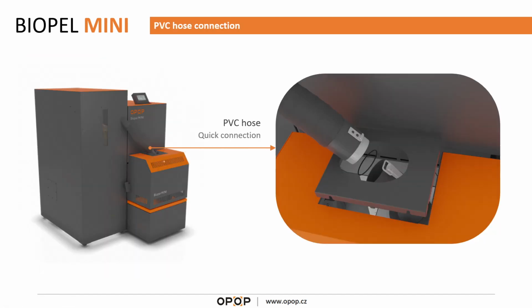Okay, like this. More about the installation on the 3D model of the boiler I will show you in a minute. There is also quick connection of the PVC hose right now. So right now you don't have to disconnect the PVC hose. You just disconnect the pipe. There are two pipes which connect together. So you just disconnect these two pipes, and you can easily remove the burner from the boiler, you know, for the maintenance or so on.